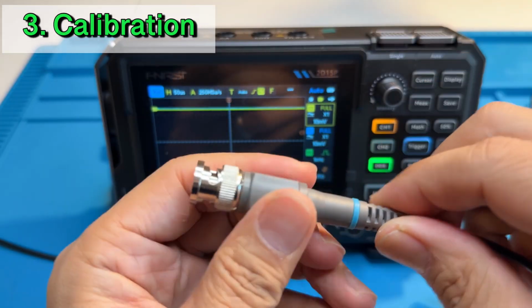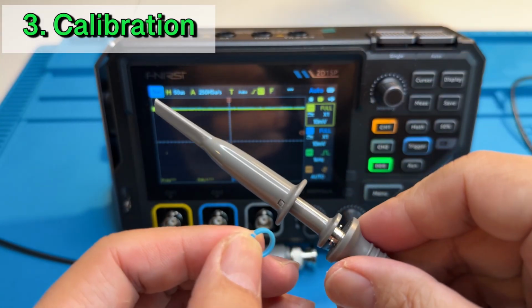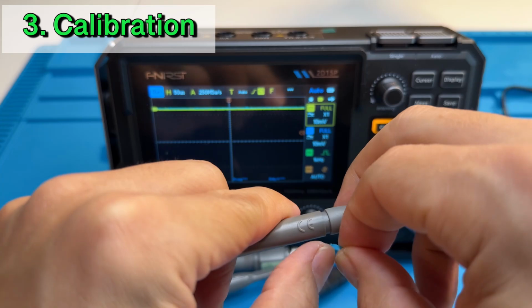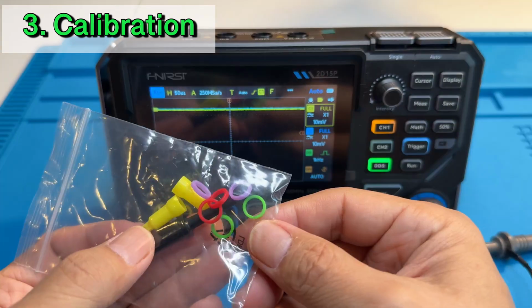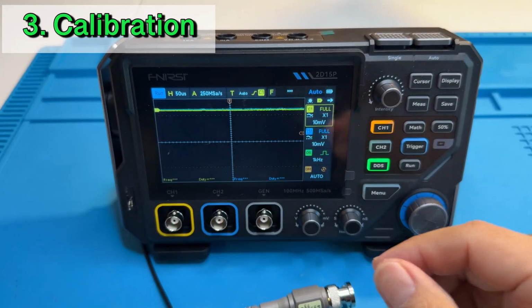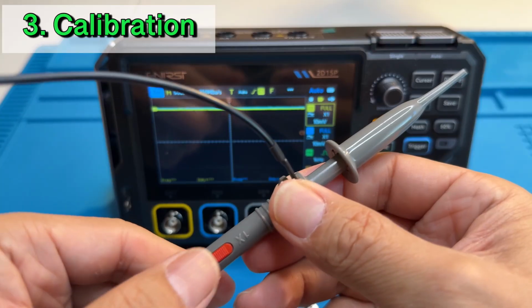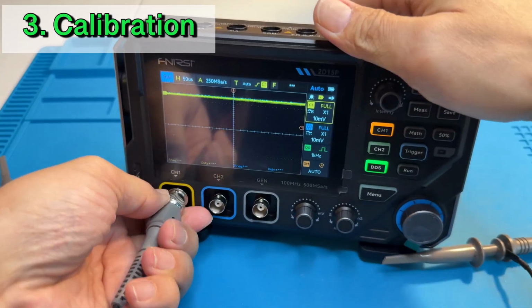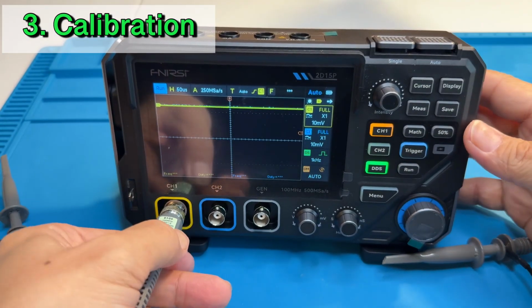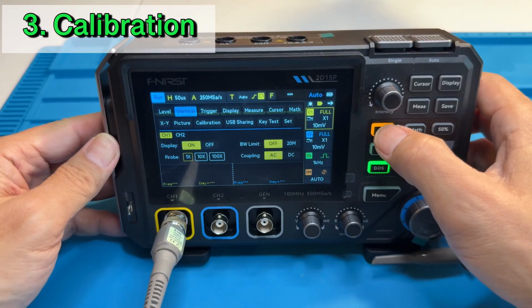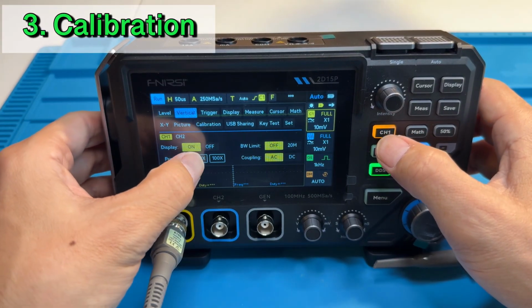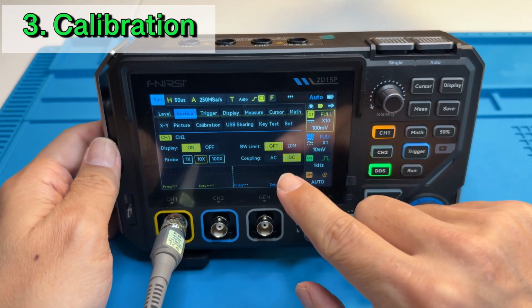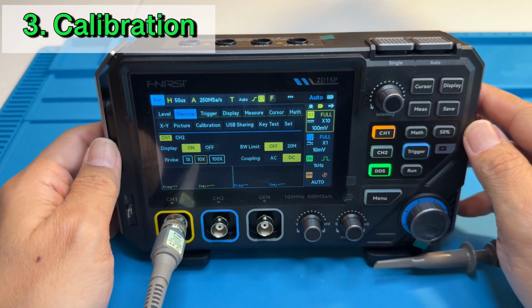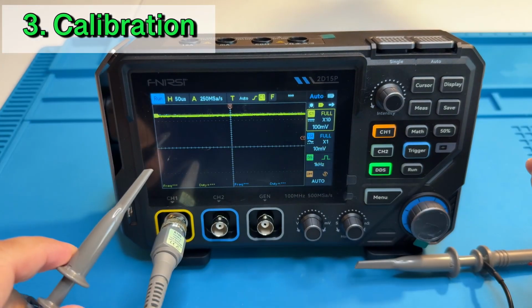Get the probe. One of the tips is I want to mark this probe so I know which one is for which channel. I use the blue ring on the probe so I can see this one is only for the blue channel only. There's no yellow ring, I'll just leave it alone. Let's start with the yellow channel. Push this to the 10 times gain on the probe itself, and go to the software on the screen and click the 10 times gain as well, to make it consistent. Also check the coupling is DC coupling. And then we're ready to calibrate.